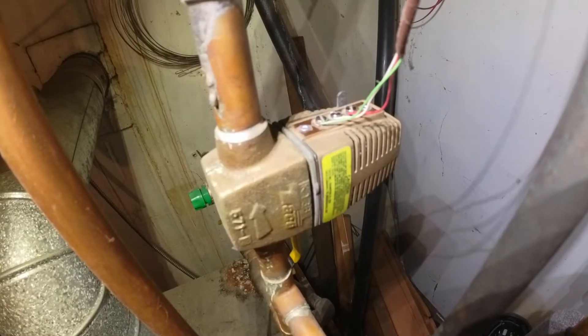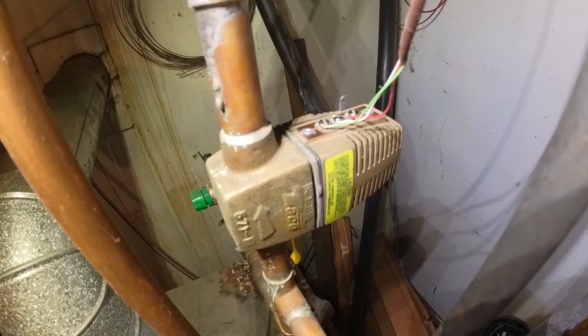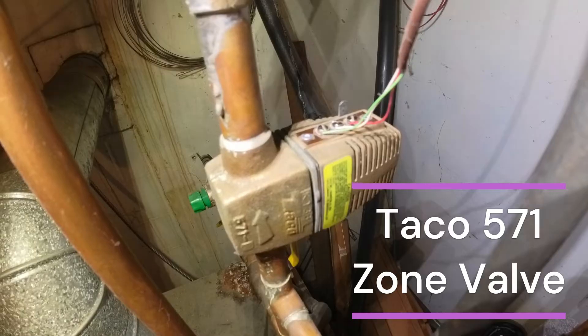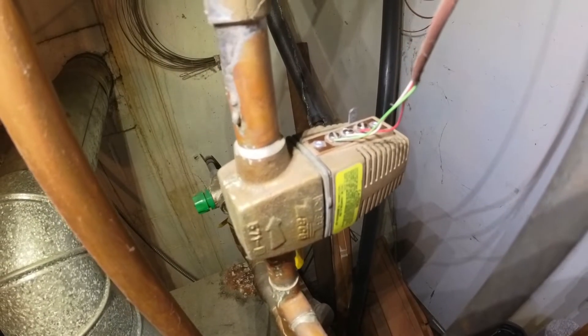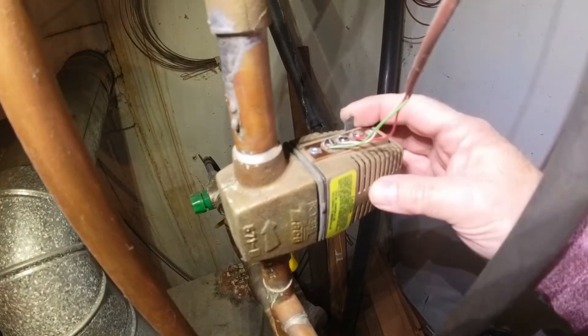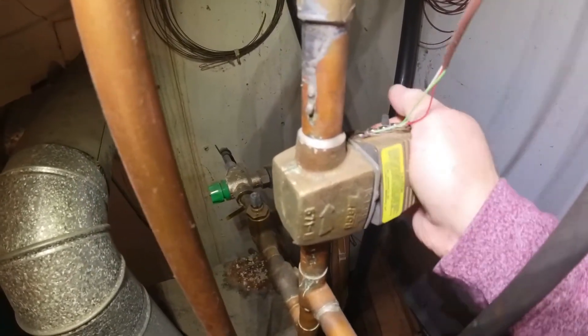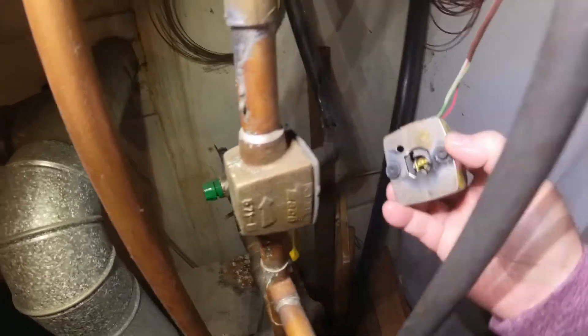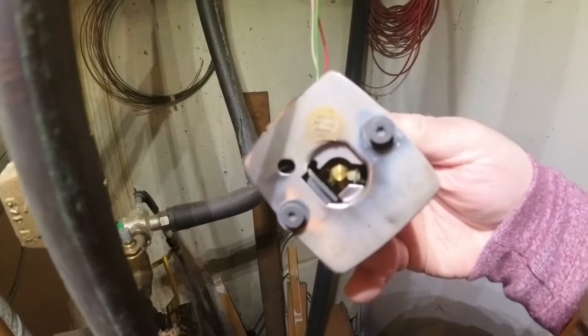I'd like to do some training today on a Taco 555 series power head and zone valve. It's a 24-volt power head running on 24-volt AC — a three-terminal zone valve with a manual lever. The manual lever is right here. You disconnect it by twisting the head and pulling off; these tabs fit into this body inside.